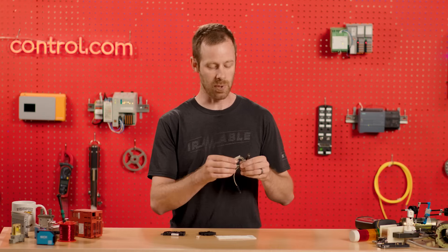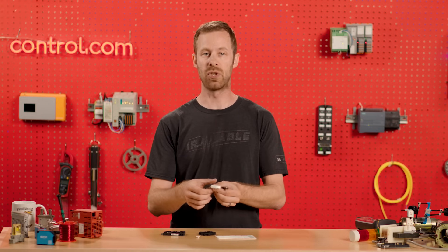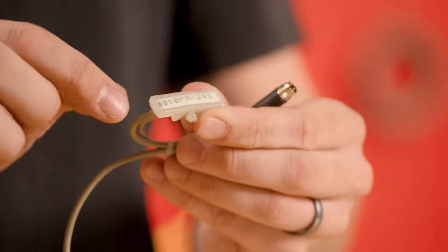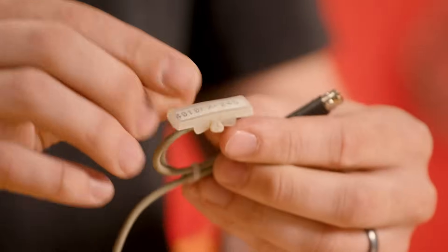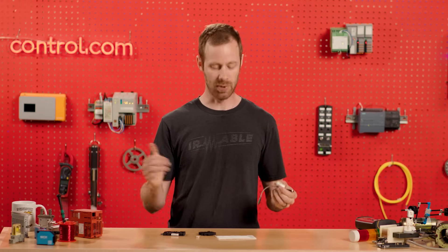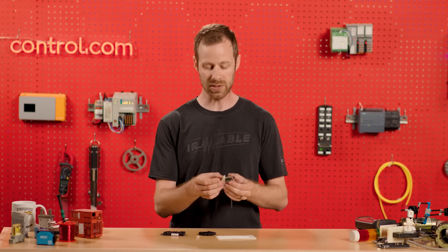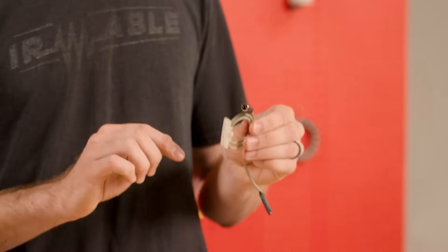There are a couple of examples of how this labeling can take place. One example is attaching labels directly to a wire itself. Sometimes this can be done with small plastic housings and zip ties — a label is affixed to the front of a small plastic block and then zip tied to a coiled wire or a long piece of cable. At either end, you can look at that cable and understand what's going on. Sometimes sleeves are shrink-wrapped around the wire so that it permanently stays in place without the extra bulk of the wrapper and the zip tie.